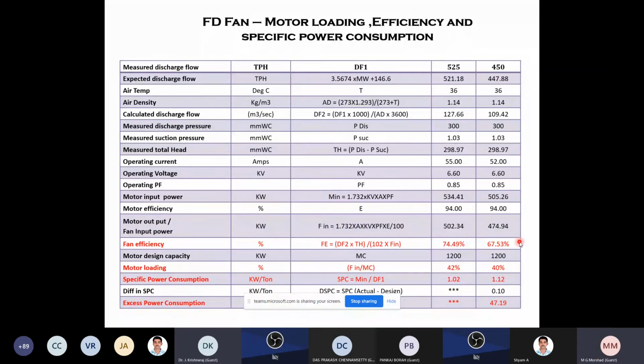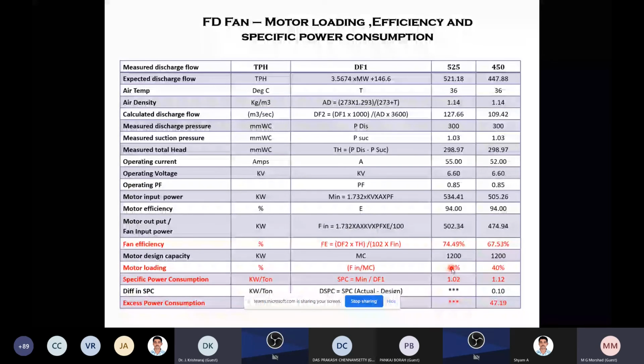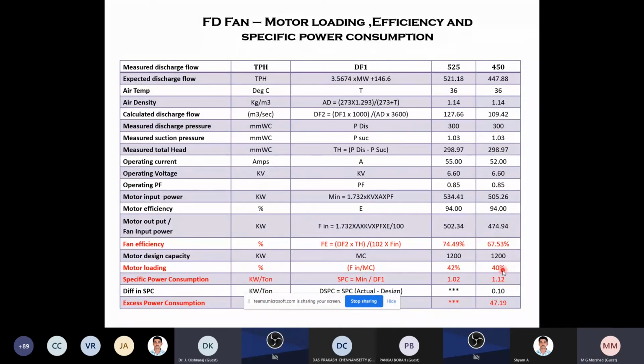What is the fan efficiency? What is the design and what is your actual operating? You see the design is 74, but you are operating at 67. After that, you have to go for the motor loading. What is the percentage? See, percentage motor loading is 42. Normally, the designer has given a higher value, but you are loading at 40. Specific power consumption, the designer has given 1.02, but you are operating at 1.12.